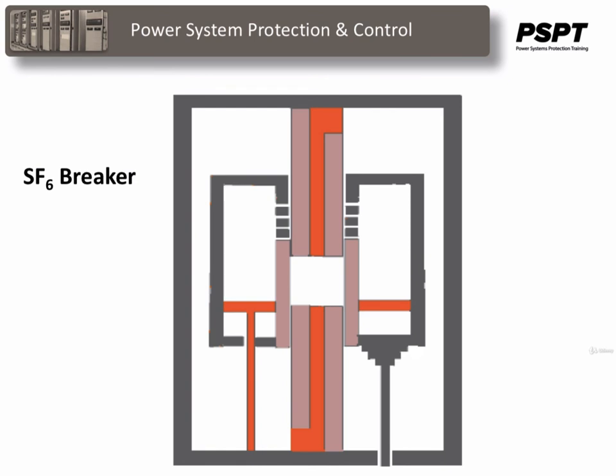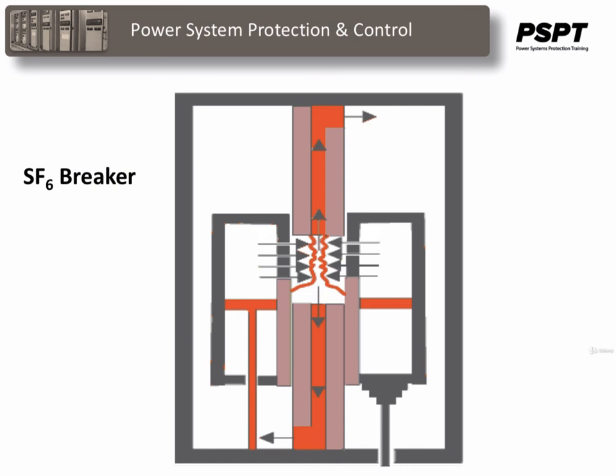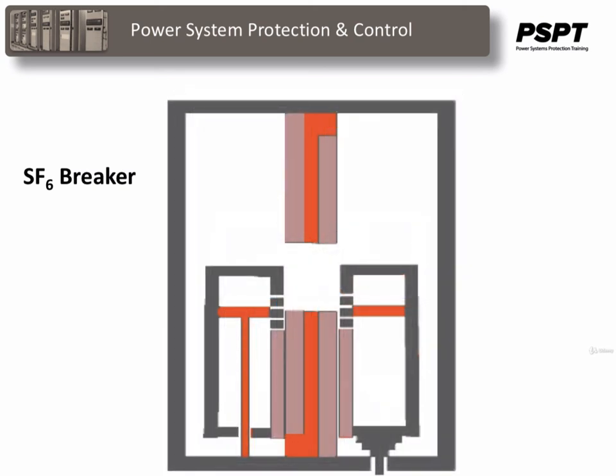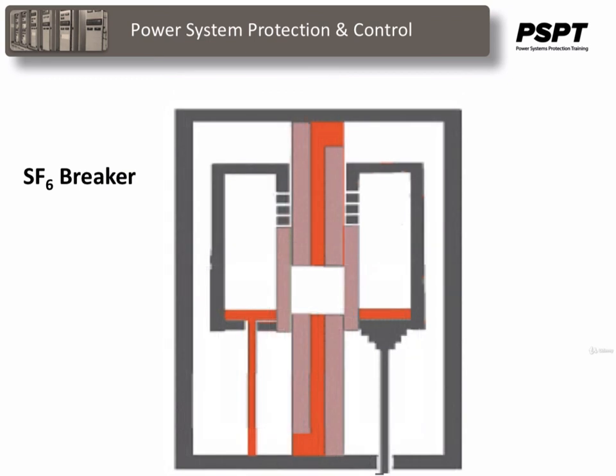During operation of the breaker, the cylinder moves downwards against the fixed piston. Hence, the volume inside the cylinder is reduced, which produces compressed SF6 gas inside the cylinder. The cylinder has a number of side vents which were blocked by the upper fixed contact body during the closed position. As the cylinder moves further downwards, these vent openings cross the upper fixed contact and become unblocked. Then compressed SF6 gas inside the cylinder will come out through these vents at a high speed towards the arc and pass through the axial hole of both fixed contacts. The arc is quenched during this flow of SF6 gas. During the closing of the circuit breaker, the sliding cylinder moves upward and is ready for the next operation.